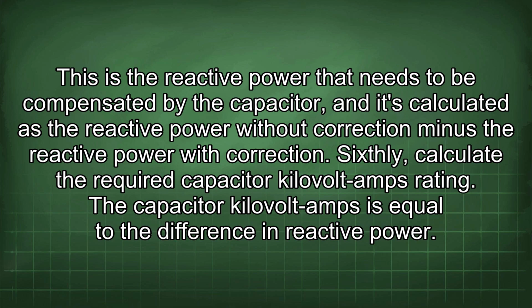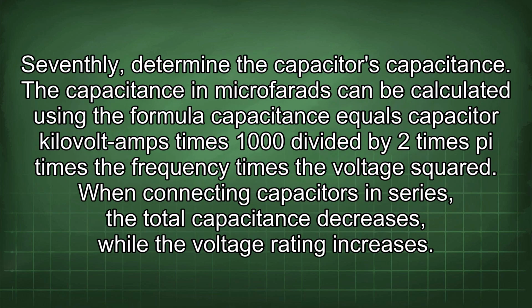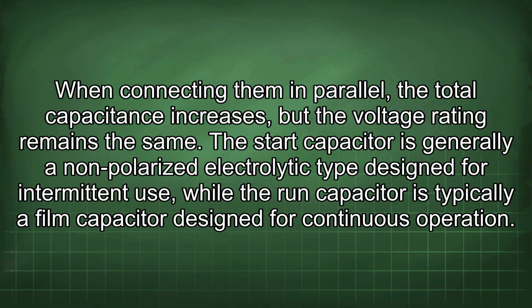Sixthly, calculate the required capacitor kilovolt amps rating. The capacitor kilovolt amps is equal to the difference in reactive power. Seventhly, determine the capacitor's capacitance. The capacitance in microfarads can be calculated using the formula capacitance equals capacitor kilovolt amps times 1000 divided by 2 times pi times the frequency times the voltage squared. When connecting capacitors in series, the total capacitance decreases while the voltage rating increases. When connecting them in parallel, the total capacitance increases, but the voltage rating remains the same.